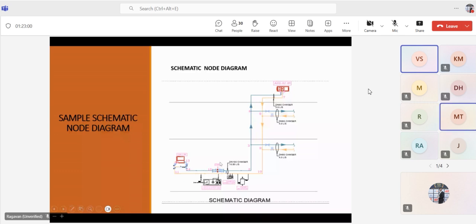Okay. Sir, I have one more question. The schematic diagram shows one pump, but in some cases we use two pumps, primary and secondary pumps, a primary-secondary chilled water system. In this case, I have noticed that people consider the critical path in different ways. For the secondary pump, some consider the critical path from the secondary pump to the equipment, I mean the load, AHU or FCU, or someone considers the secondary pump to the primary pump suction. So which one is correct, or what is the difference? Can you please explain?